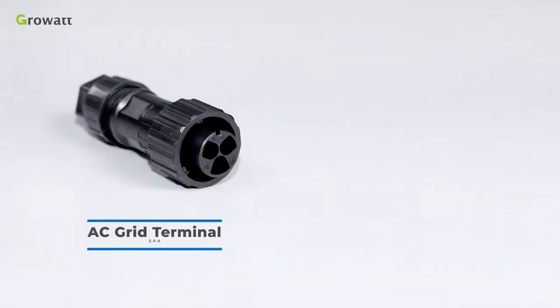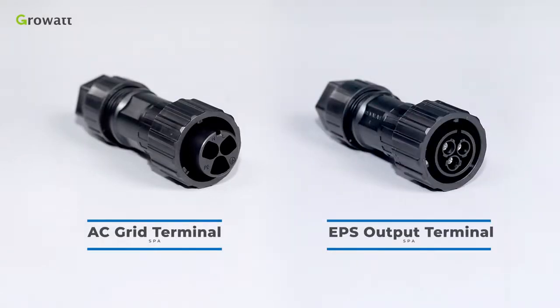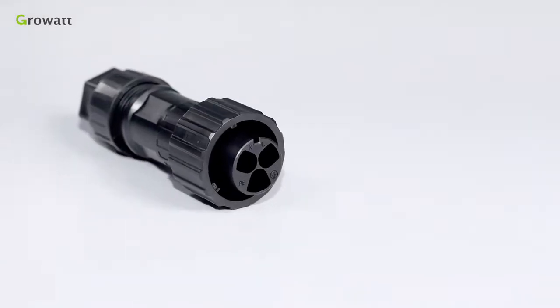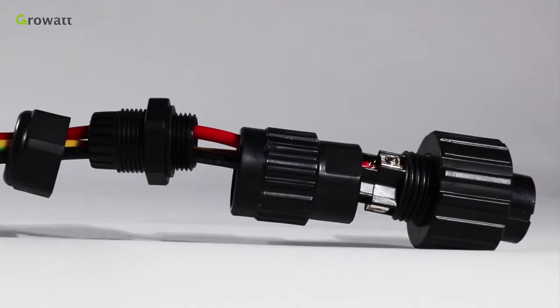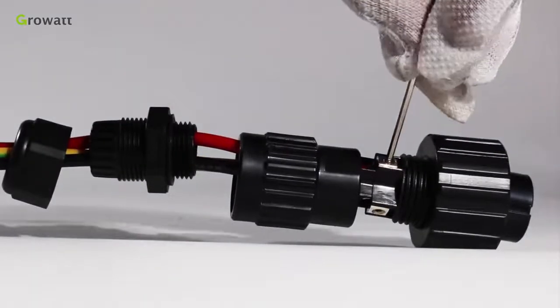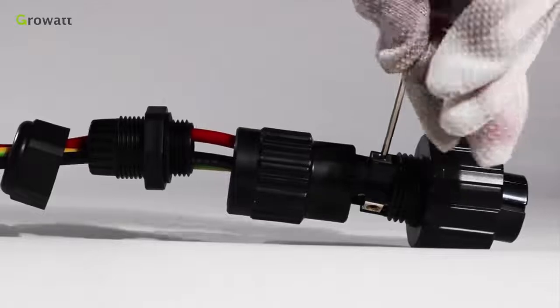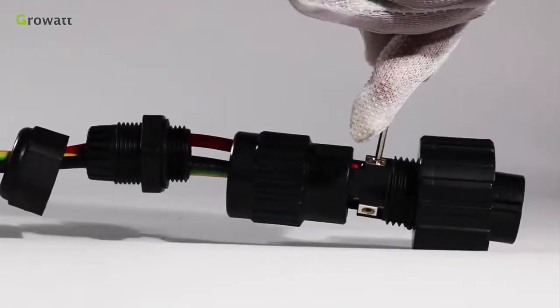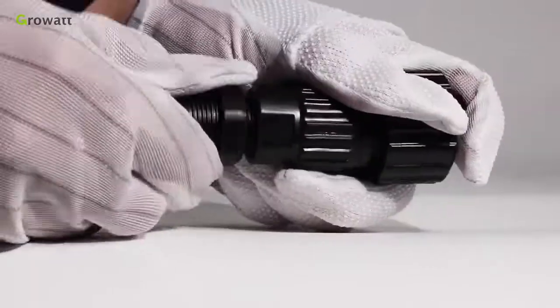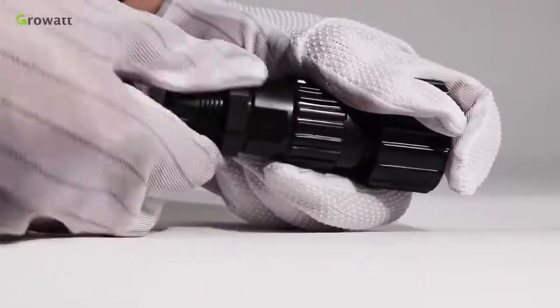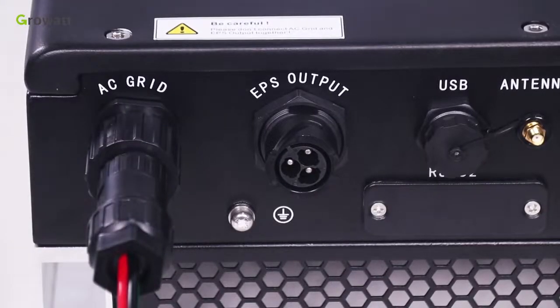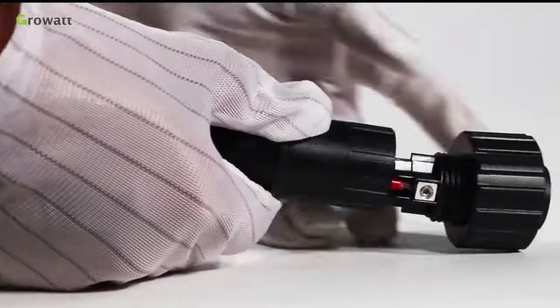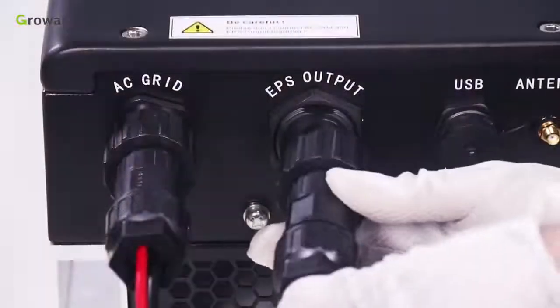SPA has an AC grid terminal and EPS output terminal. They have different appearances. Firstly, please confirm the L-N-PE port of the connection terminal. Then thread cables through pressure screw, sealing ring, threaded sleeve in sequence. Insert cables into connection terminal according to polarities indicated on it and tighten the screws. Push and rotate the threaded sleeve onto connection terminal until both are locked tightly. Plug the socket into AC output terminal. Clockwise rotation to tighten the socket. Counter-clockwise rotation to loosen the socket. The EPS terminal connection is the same as the on-grid terminal installation.